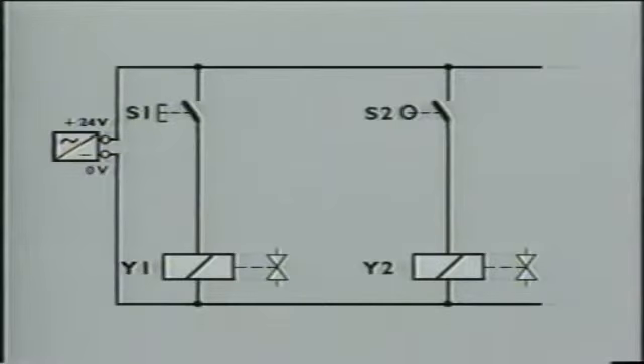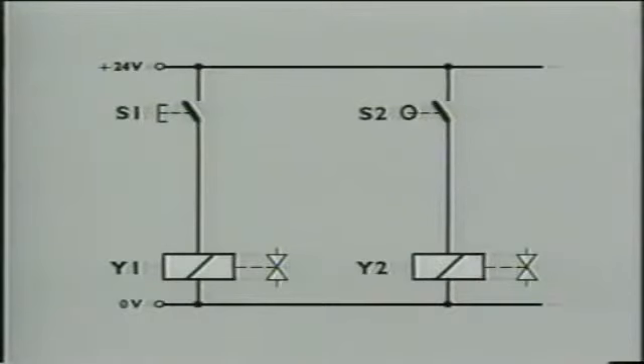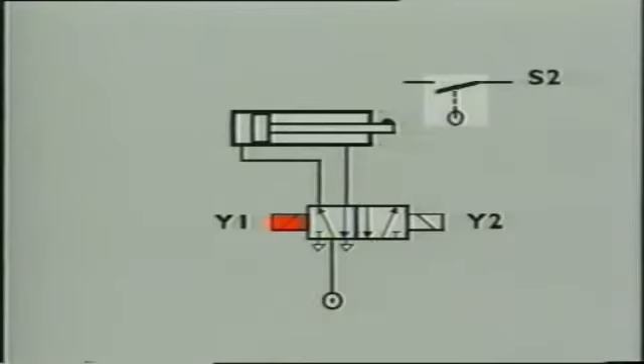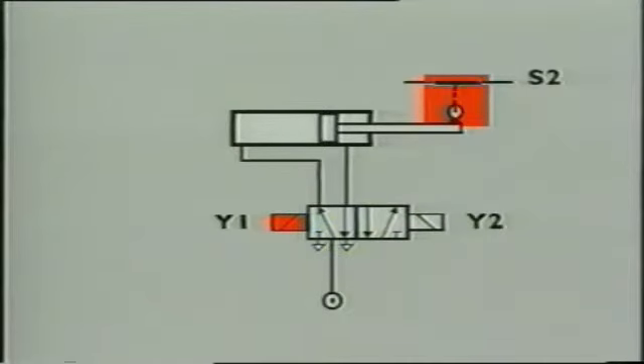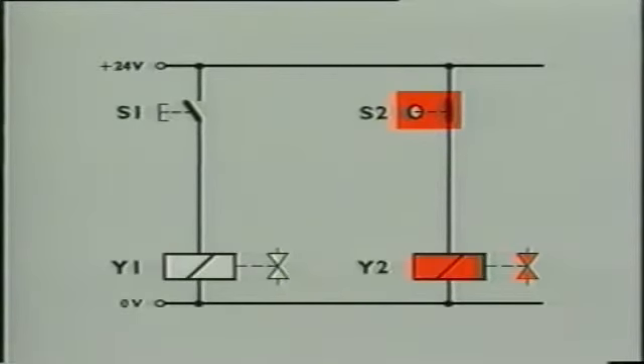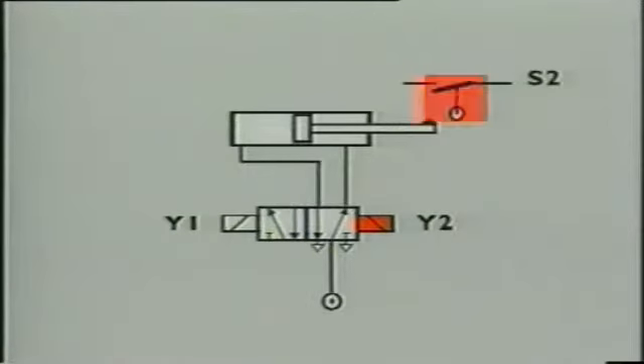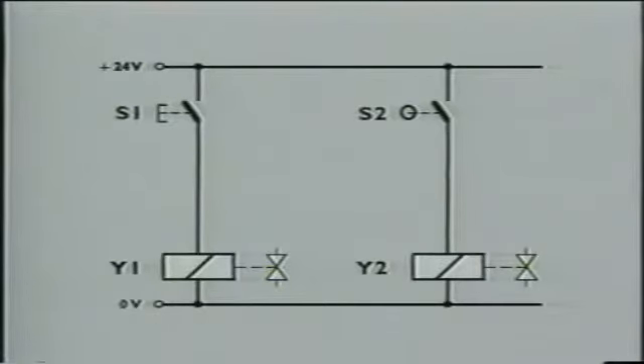And this is the corresponding electrical circuit diagram. You can see two 24-volt circuits. To simplify the diagram, the circuit diagram does not show the voltage source, in this case the power supply unit. If push button S1 is pressed, coil Y1 is energized. This switches the valve and the cylinder extends. In its forward end position, the piston actuates the limit switch S2. This closes another circuit, energizing coil Y2, reversing the valve. The cylinder retracts. When the valve is directly controlled in this way, control circuit and power circuit are identical.